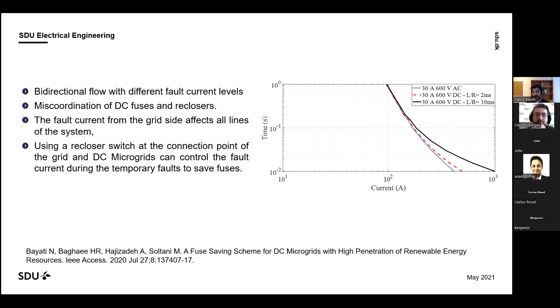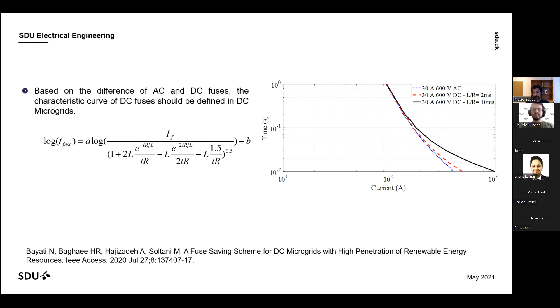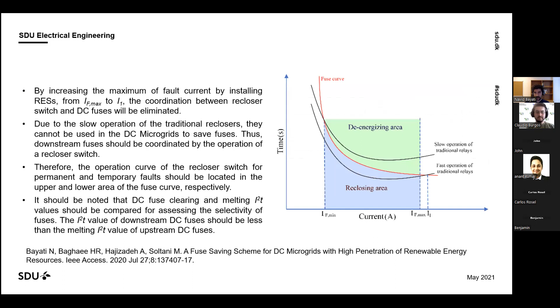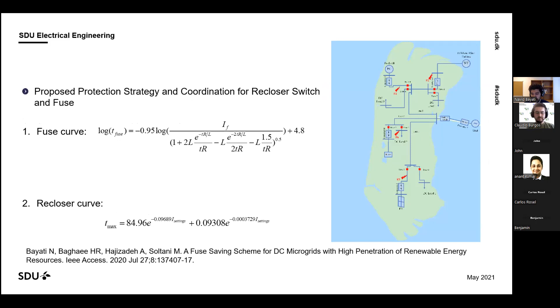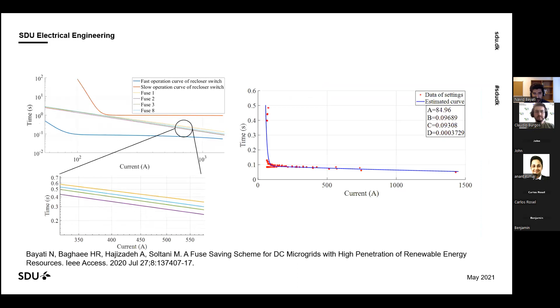So here we selected the fuses with different settings that are made for DC systems. Normally when we talk about fuses, the equations and curves are made for AC systems, but here we changed that for the DC system. We saw that the behavior of the fuses on AC and DC systems is different, so we can have new or different coordination for the fuses. Here also you can see that if we want to make coordination between the fuse and recloser, we can put the fuse curve between the recloser curves. If we apply the method on this simulation of a DC microgrid, we saw that this coordination can save fuses, and you can see the data collection and the different behaviors of the fuses here.